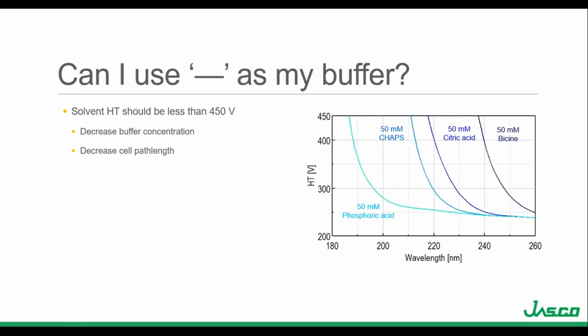One of the most common questions I get is: can I use my buffer as a blank? The best way to check is to run a measurement of the buffer in the wavelength range you want. Since we want the buffer to contribute very little to the overall absorbance, the solvent HT voltage should ideally be less than 450 volts — any larger and the addition of the sample will likely surpass that 700 volt threshold. The figure on the right illustrates different solvents and their wavelength limitations. If I wanted to go below 200 nanometers, my only option is a 50 millimolar phosphoric acid buffer.